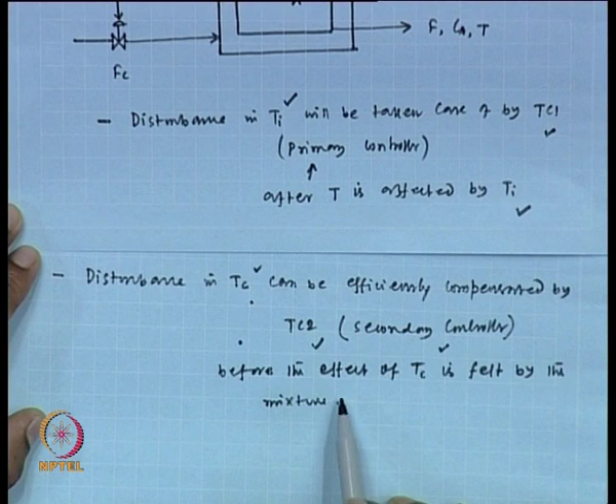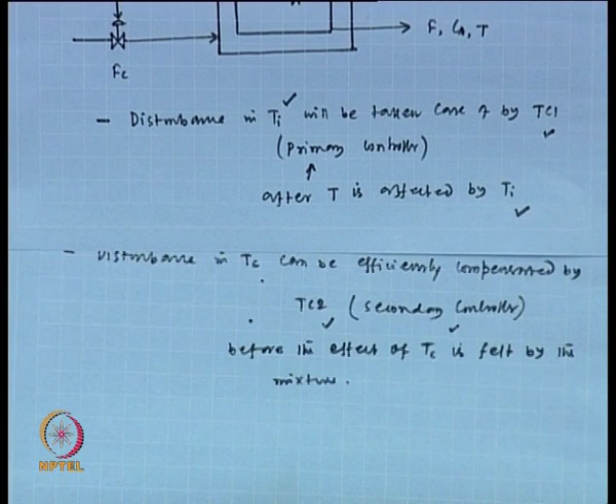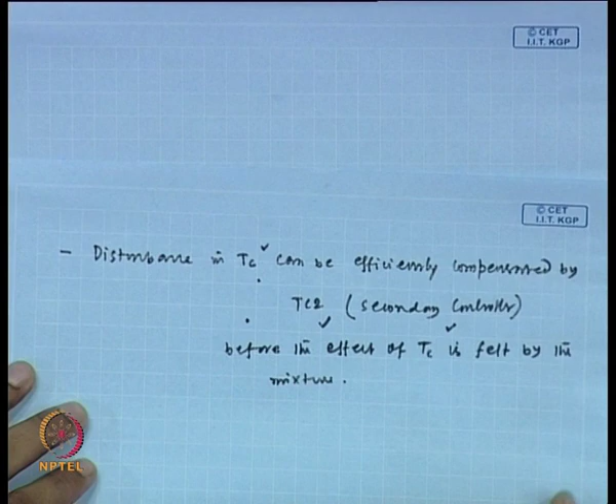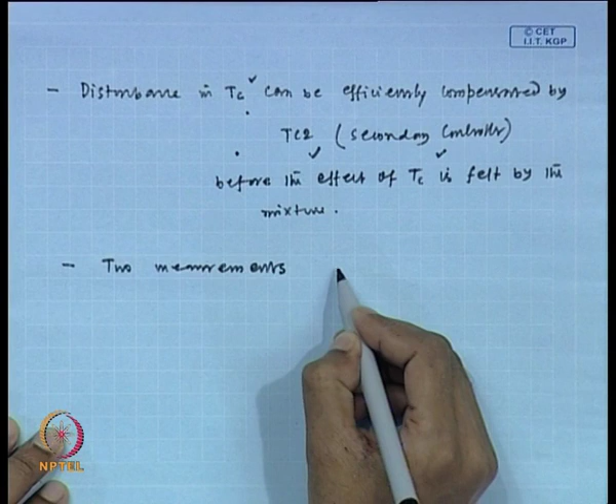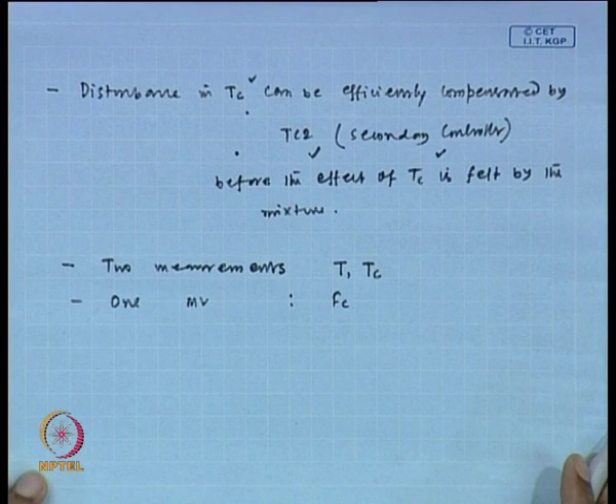So, previously I mentioned that there are two possible disturbances, one is Ti, another one is Tc. Now, if there is any change in Ti, that will be taken care of by TC1, and if there is any disturbance in another load variable Tc, that can be efficiently compensated by secondary controller TC2. Fine, but the primary controller takes action after T is affected by Ti, and the secondary controller takes action before the effect of Tc is felt by the mixture. So, here two measurements are involved. One is T, another one is Tc. But the manipulated variable is one, that is Fc.